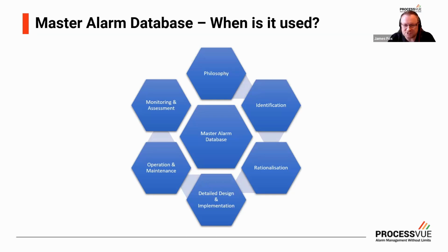Detailed design and implementation. From an implementation point of view, it provides the ability to ensure that the correct configuration is applied to those alarm systems. But it also goes one step further than that, because it gives us the opportunity to make sure that if we're modifying the plant or we're upgrading the plant of the process, it allows us to optimize the alarms for that modification up front, which saves us time from having to do expensive alarm rationalization activities later on. It's sort of a get it right first time mentality.